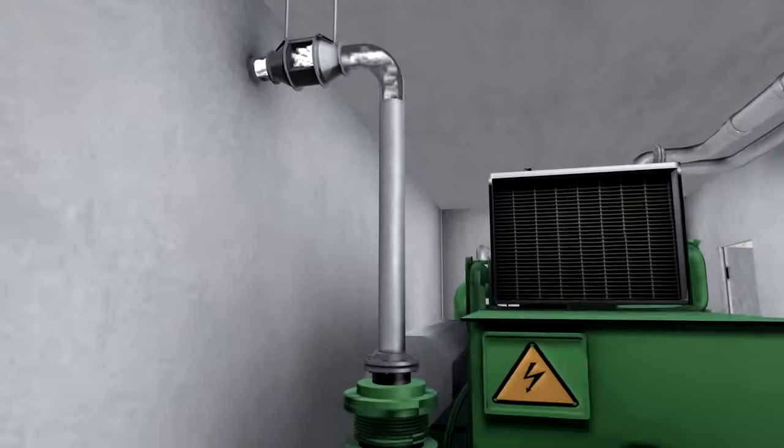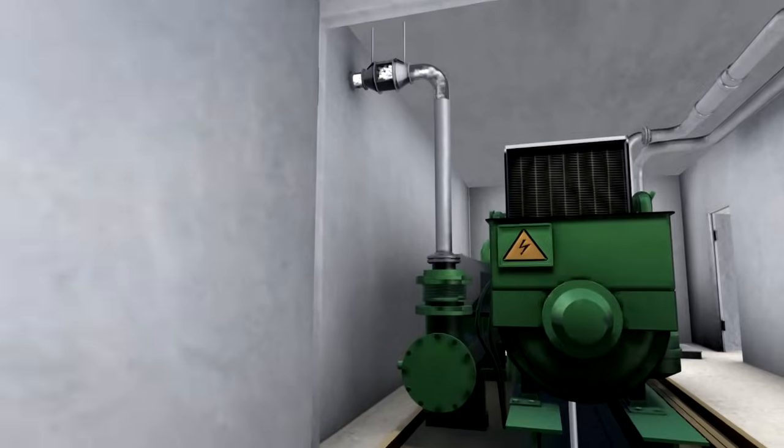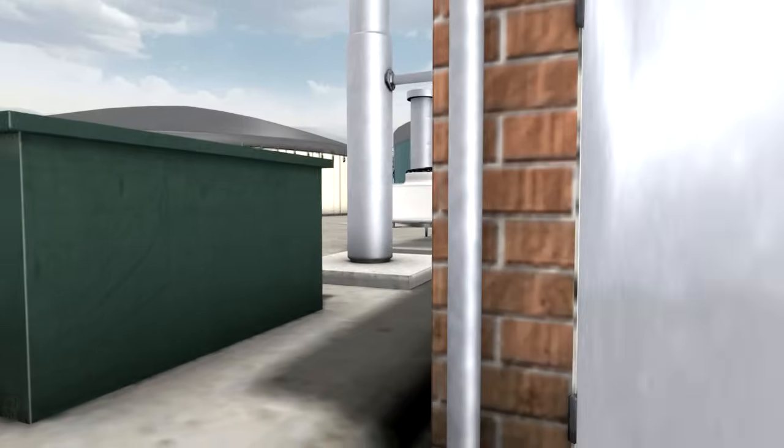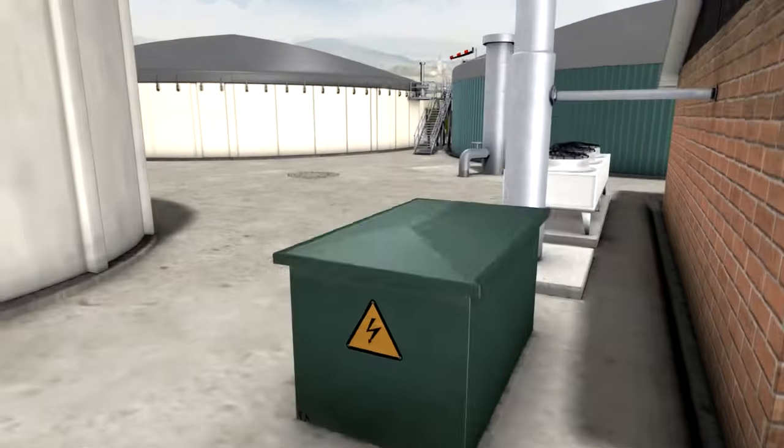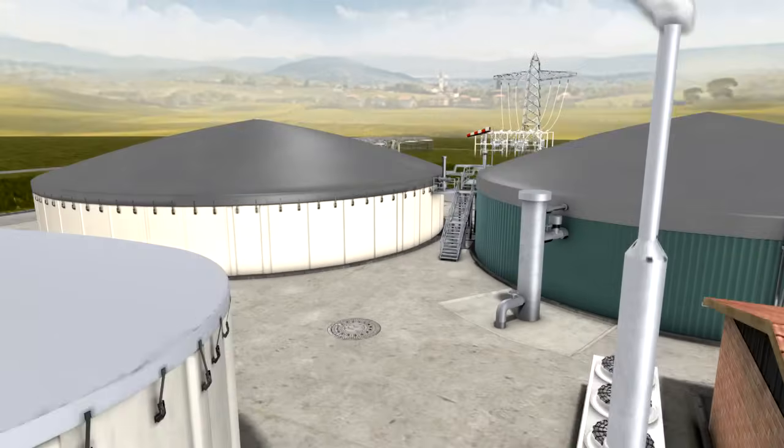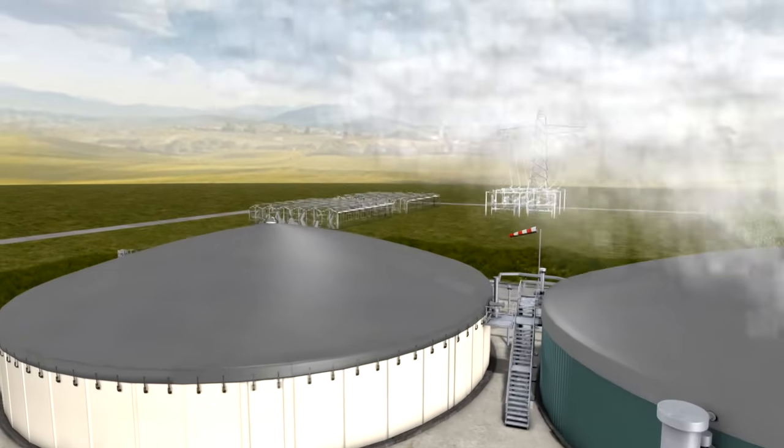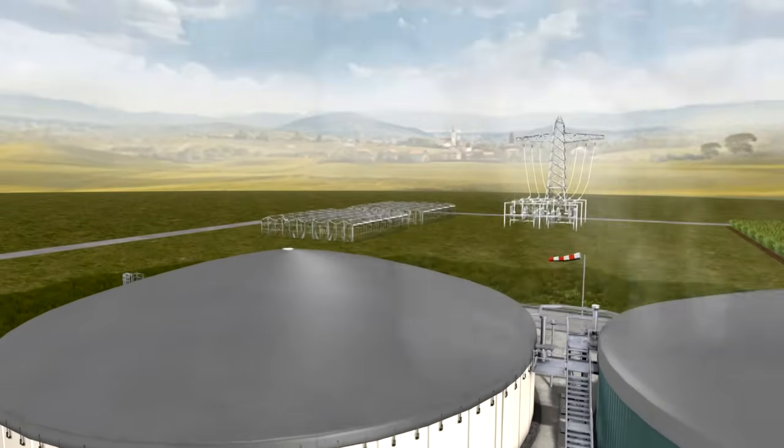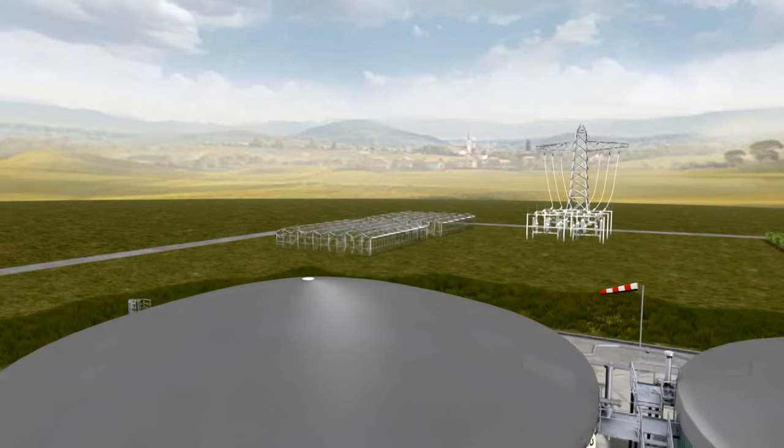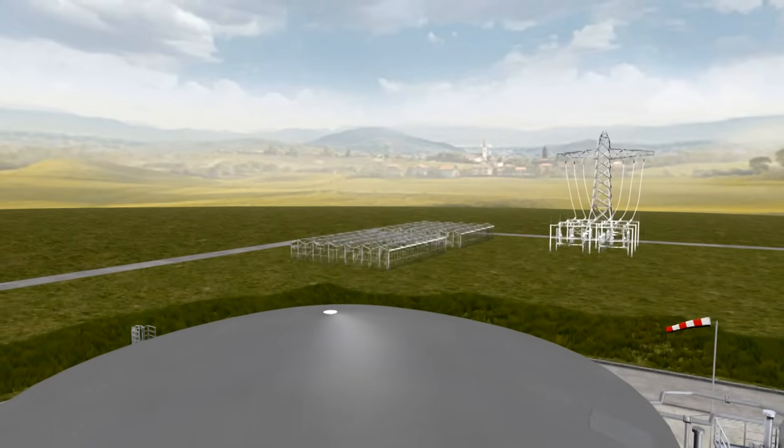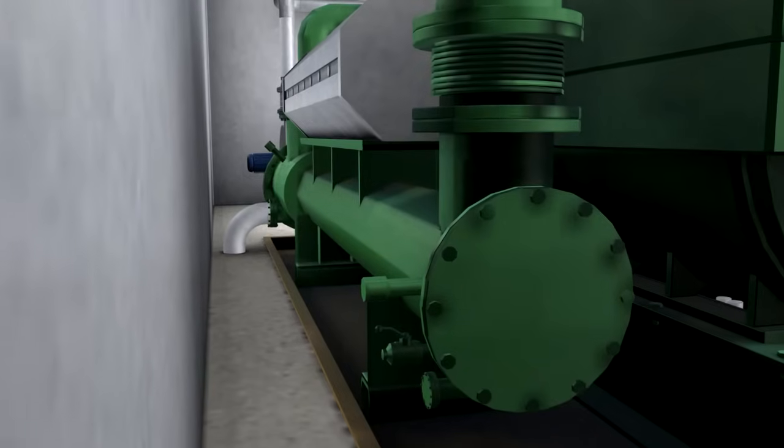The generated electricity is fed to a transformer at mains voltage and then supplied to the public network on site. The thermal energy can be used for heating buildings and stables, greenhouses or for the heat supply of the entire residential area, depending on requirements and the size of the plant. Part of the heat is then fed back into the process for heating the fermenter.